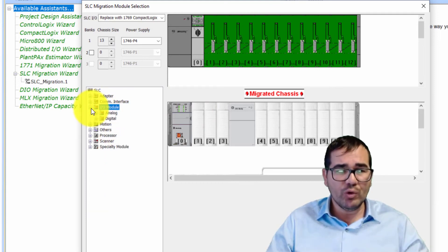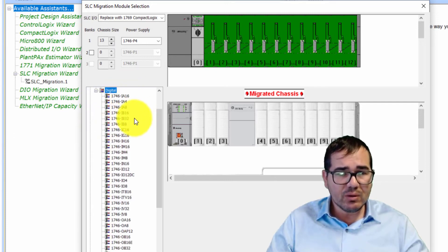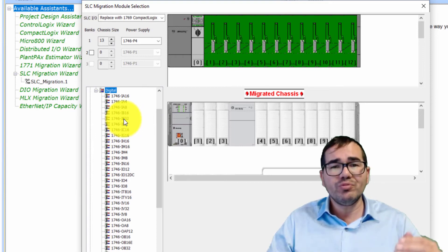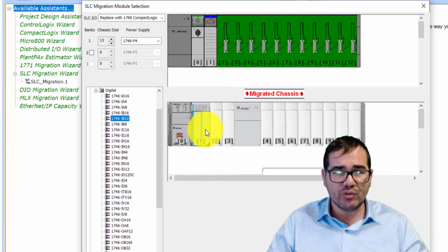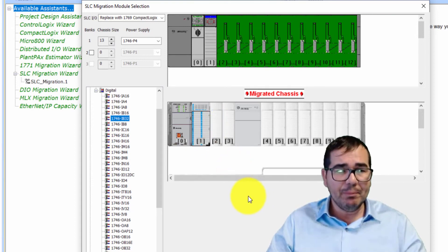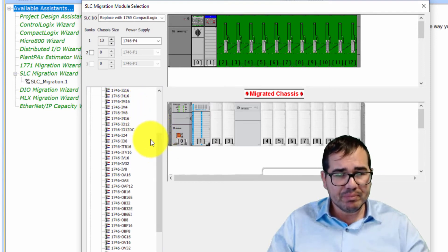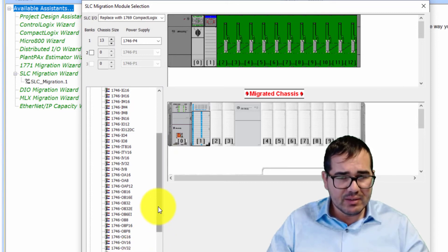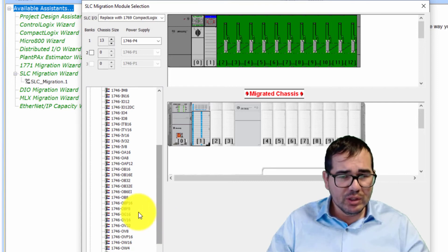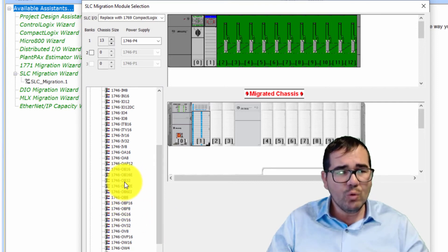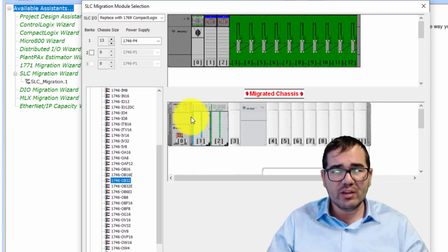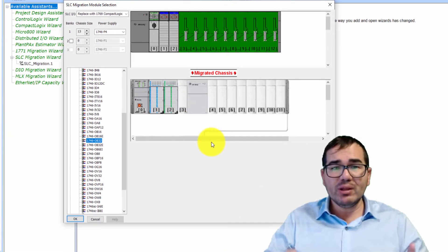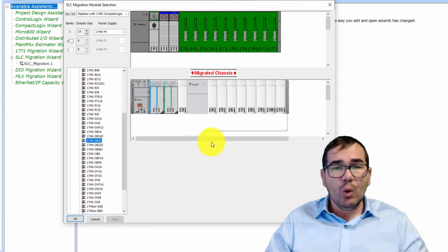The fourth step is to choose the I/O modules. I'm going to select digital inputs — the IB32, which is a 32-point digital input card. Automatically, you get the CompactLogix equivalent shown alongside it. I'll also add an output card — the OB32, a 32-point digital output — and again, automatically you see the matching CompactLogix module. It's very easy to do step by step.